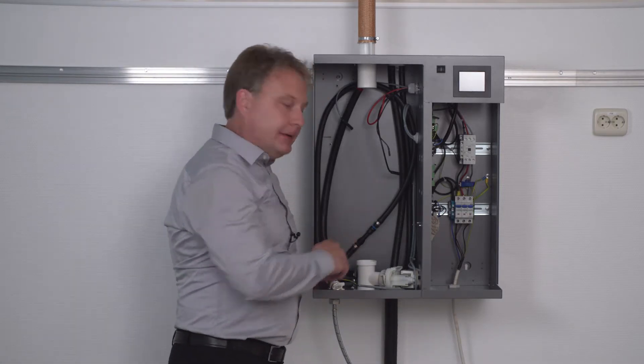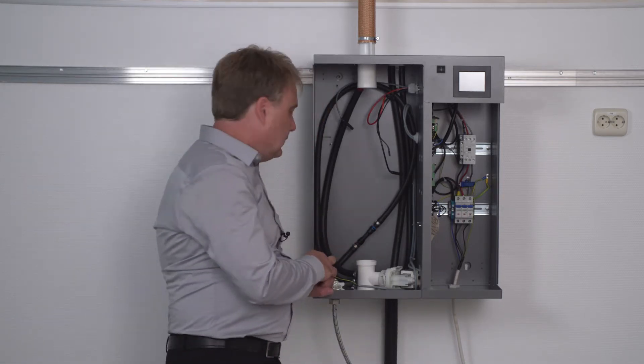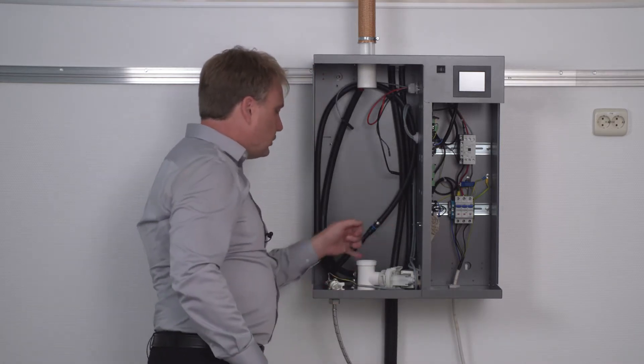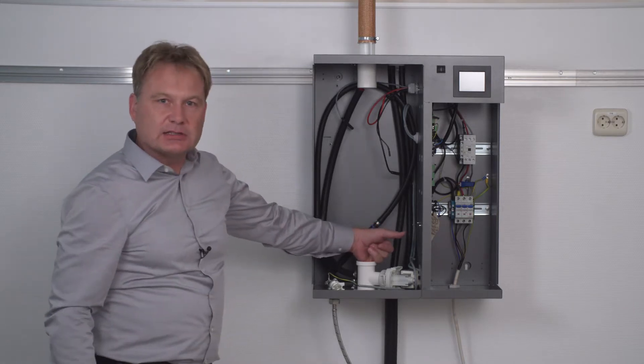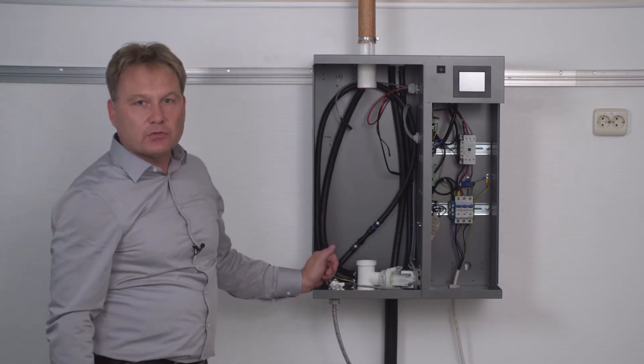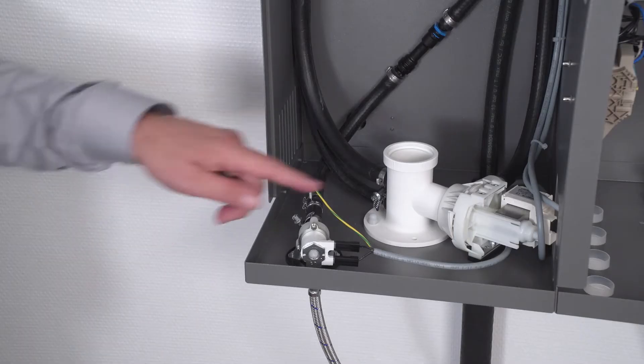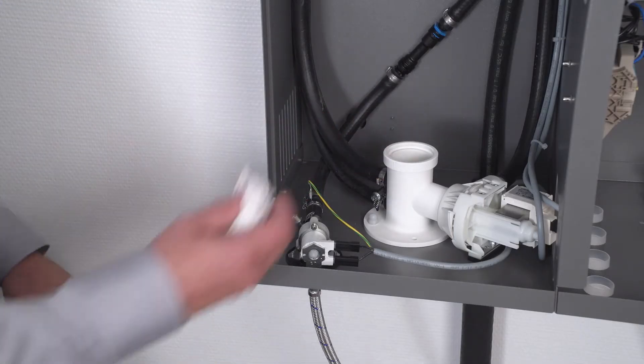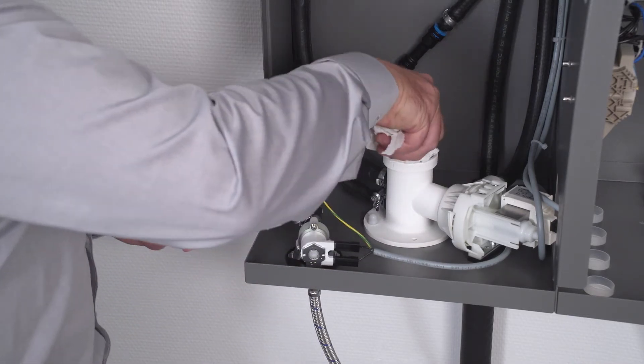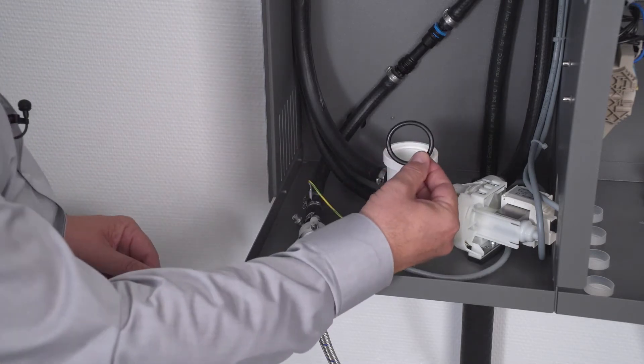Then I look into the cylinder base. If there are mineral deposits. If the hole here is clear, the blow down pump. If there is anything, mineral deposits, please remove them. In that case, you might have to remove the base and clean it properly. Then please clean the groove of the cylinder base as well with a cloth. And insert a new O-ring into the groove.